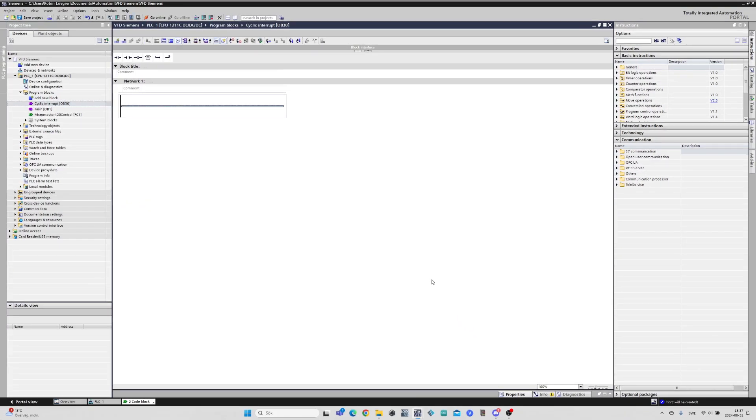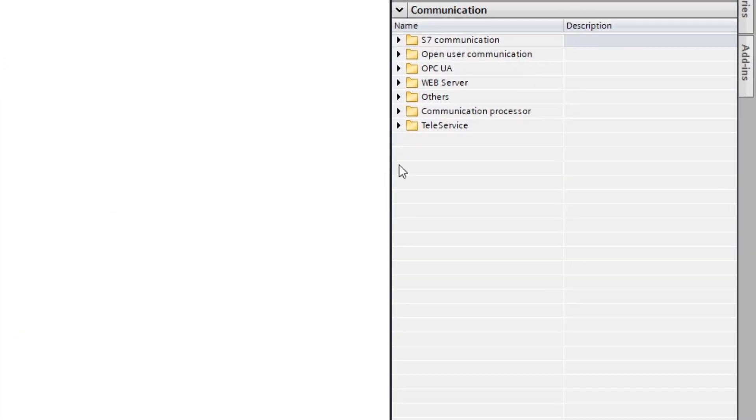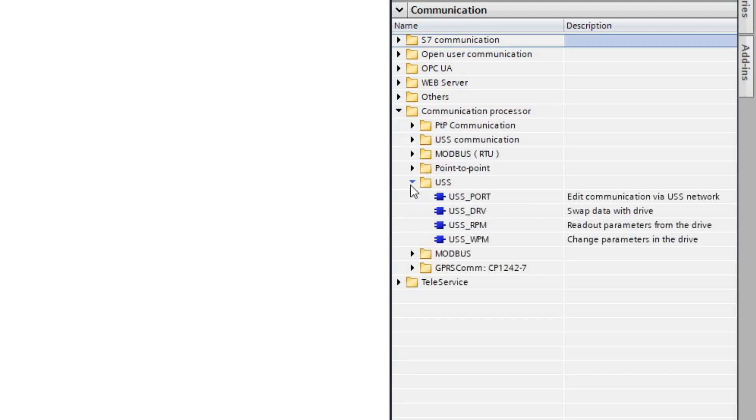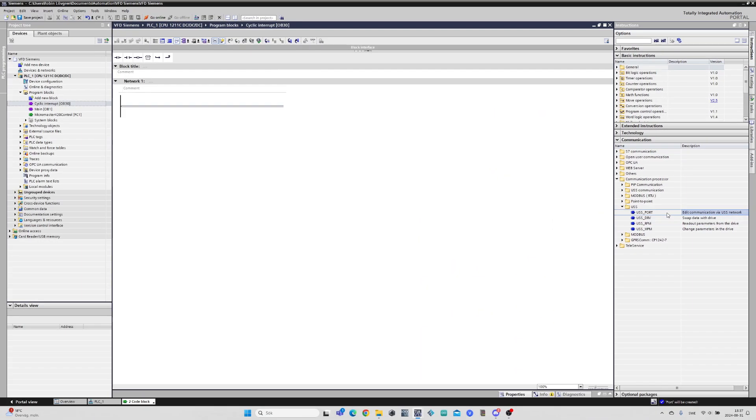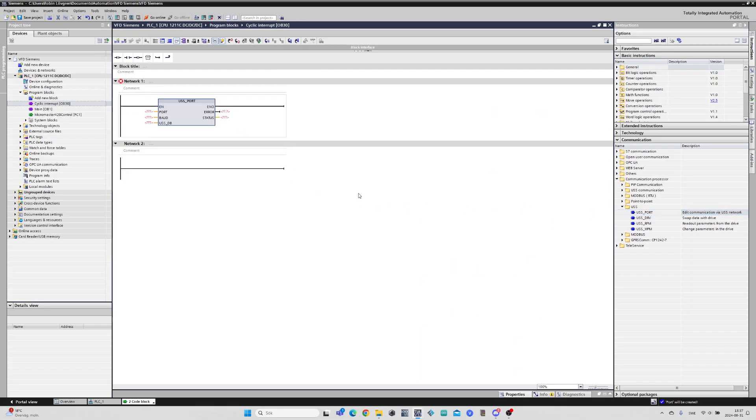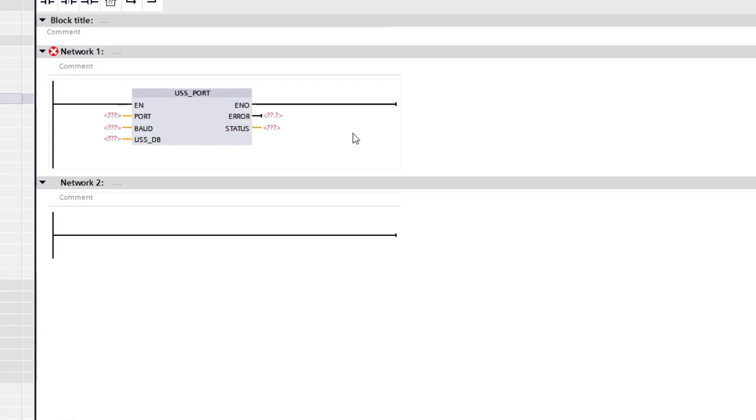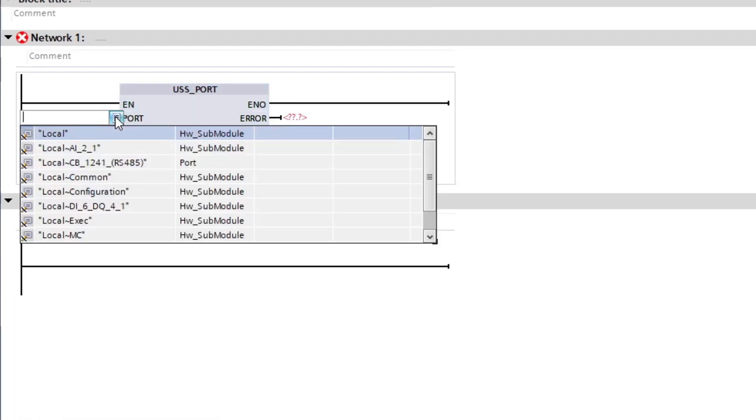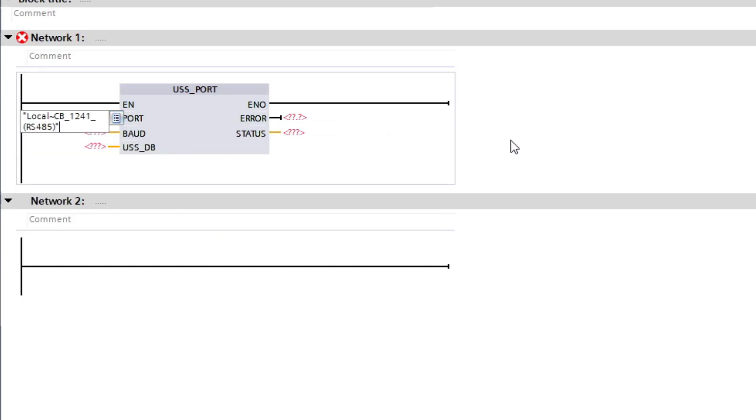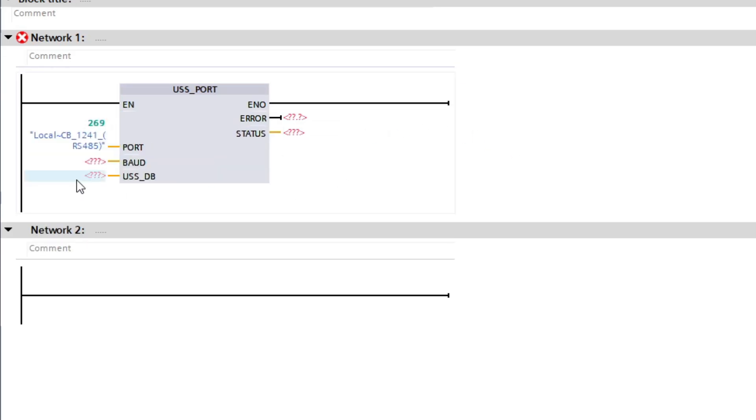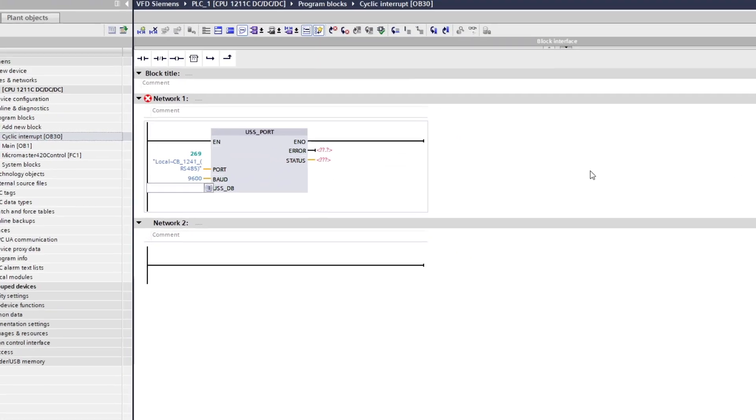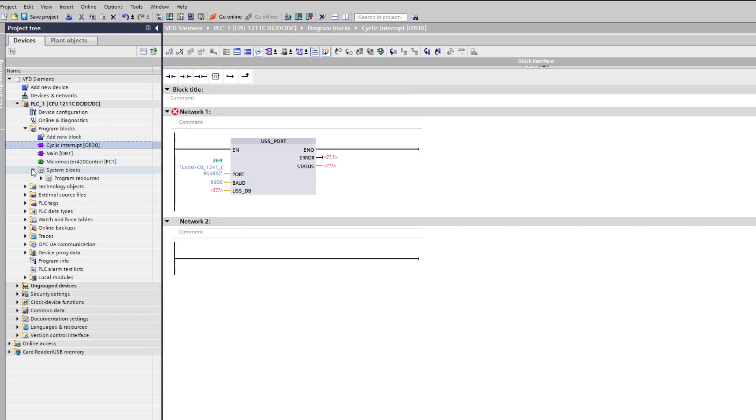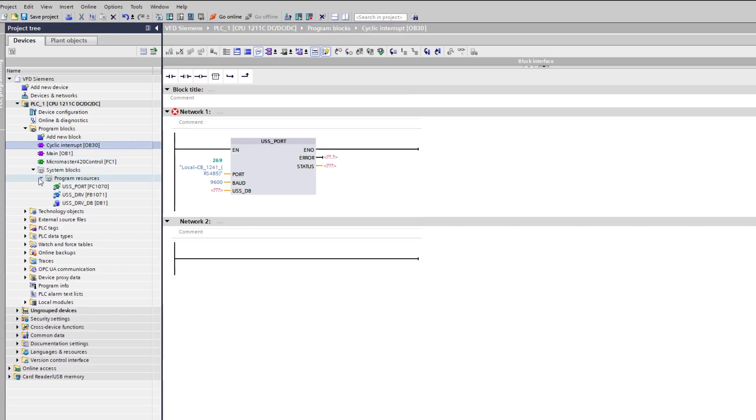Here I will add the USS port block. On the port input we want to add the RS-485 card from the PLC. And the baud rate input we want to set to 9600. To the last input we want to add the data block TIA Portal made for us from the drive function block.